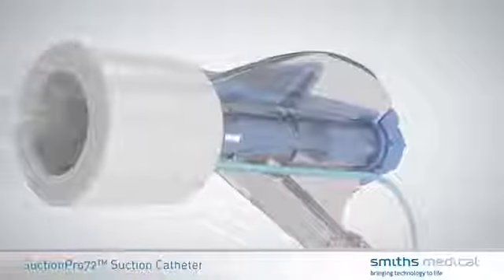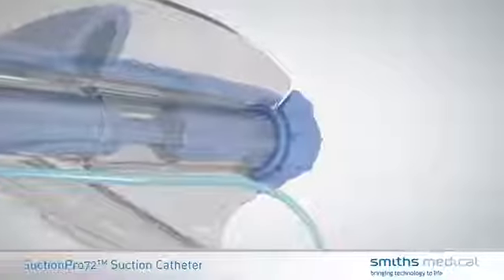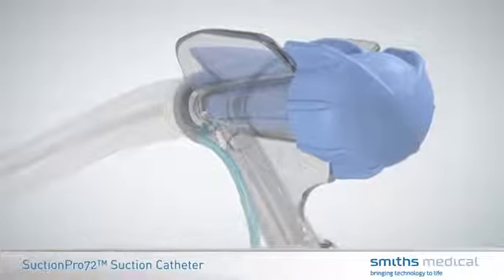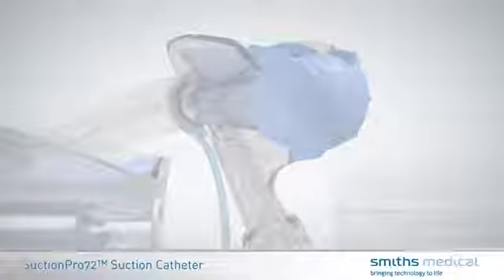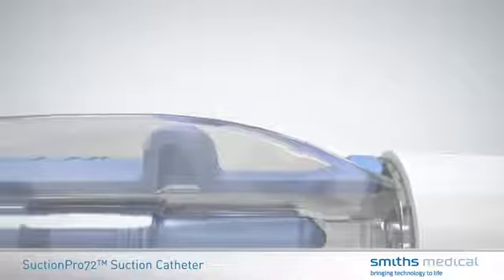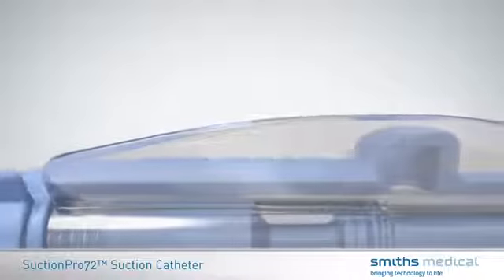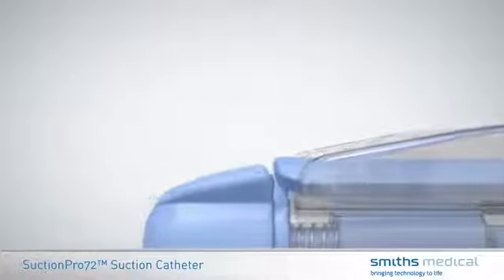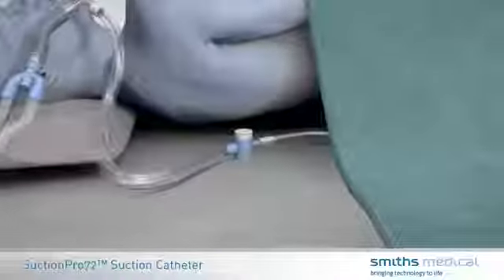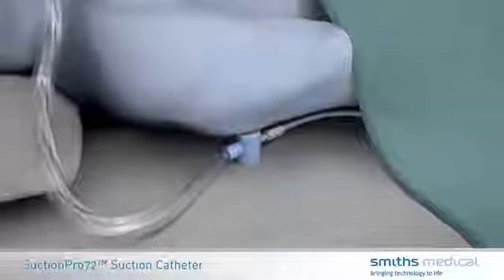The thumb valve is made of a clear material, allowing operators to visualize the complete removal of all secretions from the catheter during suctioning and cleaning. The clear thumb valve material provides visual confirmation that the suction piston has reverted back to its closed position, and the catheter is completely sealed from inadvertent suction. Elevated safety wings provide a secure guide for the thumb valve actuator and prevent the patient from inadvertently self-suctioning. More traditional push-button thumb valves may be inadvertently activated by patient movement, such as rolling onto the thumb valve.